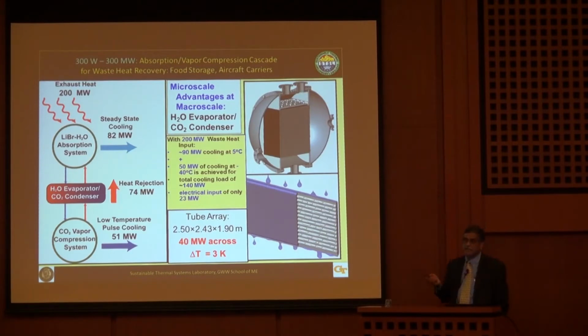You take a typical shell and tube heat exchanger, replace the tubes with flat tubes, and do falling film evaporation on the outside. This is a high heat transfer coefficient internal condensation process. CO2 is an excellent fluid, and condensation is a very nice process, so you get excellent heat transfer coefficient on the inside. Falling film evaporation of water, which Professor Takata has worked on, is another excellent heat transfer process. We demonstrated that in a fairly small package, about 2.5 by 2.5 by 2 meters, we can transfer 40 megawatts across a delta T of only 3 Kelvin using this.